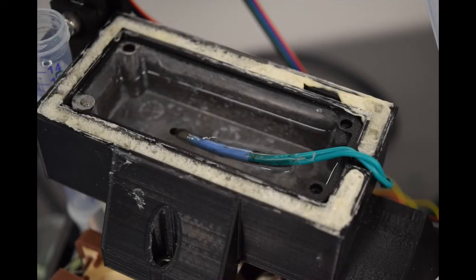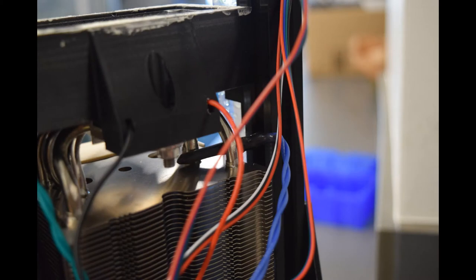To begin setting up for a sampling run, let's first put thermal probe number one into the sample block. For me here, thermal probe one has a green wire and it fits in the notch on the right side of the sample block when looking at the BioSamplr from the front. The aluminum box of the sample block should be half filled with water and/or ethanol. We've added some ethanol so the stagnant water won't grow anything. Make sure not to overfill the box as sample tubes will be inserted into it and displace some of the volume. The thermal probe should be in the water, centered so that it will be between the two rows of sample tubes. Thermal probe 2, which is blue for me here, should rest on top of the radiator and can be either wedged between the radiator pipes or taped on the top.